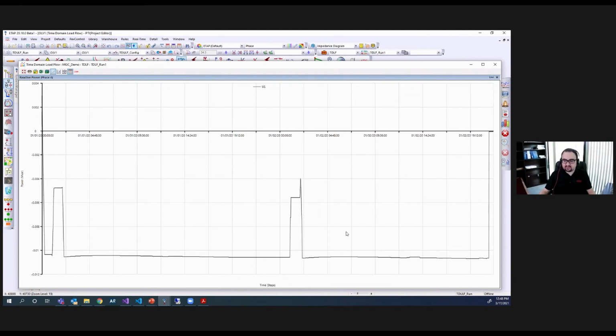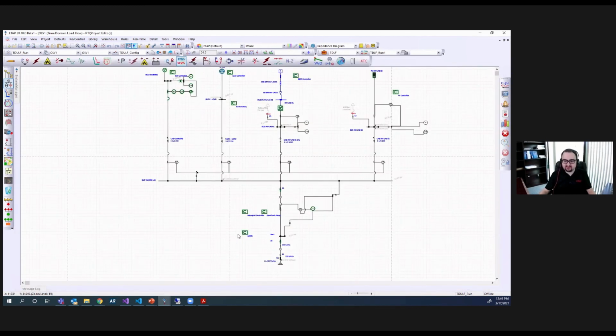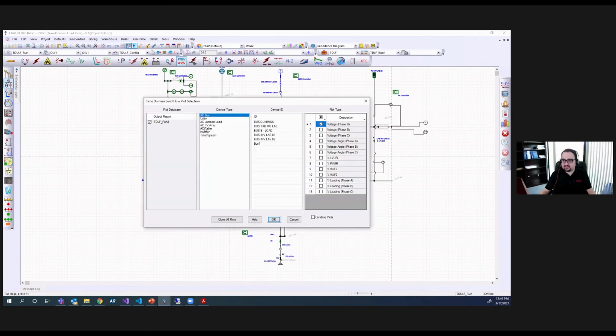The same scenario for the second day, basically. So as you can see, the Microgrid controller can effectively control the reactive power and active power at the point of interconnection, based on the modes of operation that we can set in the settings, or based on the commands that it receives from the ADMS or grid operator. So this was basically the simulation study that we do.